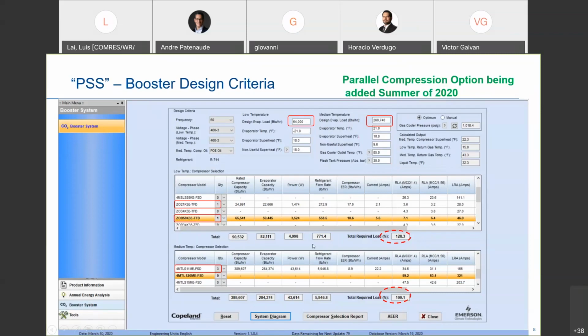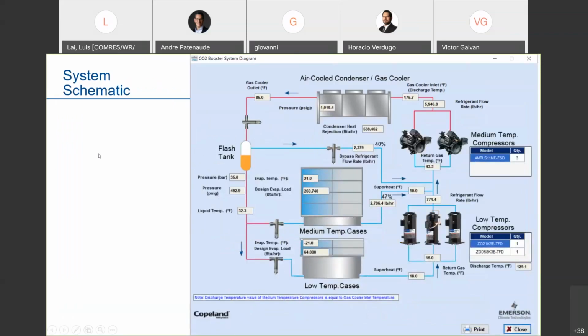Now what happens is this entire total heat of rejection from these selection of compressors automatically gets added down here to the medium temp load so that we can select the right amount of medium temp compressors to not only handle all the medium temp load, but also handle the total heat of rejection from the entire low temp circuit. And by selecting 3 of these 4 MTLS 11s, we're going to be a little bit over at 109% of capacity. And there's a nice little system schematic for customers and even us to see the flow and understand where the mass flow is going. And all the values you inputted in the screen before get shown up in here. Your gas cooler outlet, your capacity, your pressures, and so on, flash tank, they're all listed here.